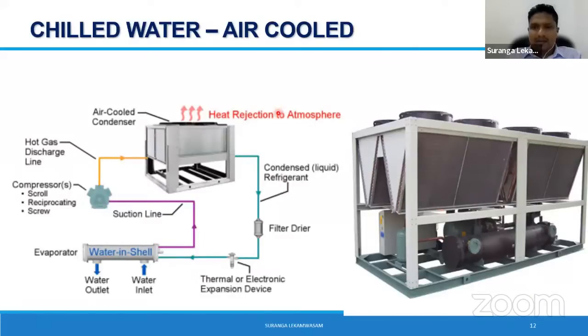They are low in efficiency, because any air-cooled machine is low in efficiency, as you are all aware. Therefore, that is not much common in Sri Lanka. But there are some applications, if you look carefully, where you cannot use water-cooled chillers. If in the area you have a water shortage, or if you have bad water quality, then this will be a choice. Again, especially in hospital applications, some of the hospital design guides recommend going for air-cooled chillers, not water-cooled chillers, because when you go for water-cooled chillers, at the cooling tower there is a risk of Legionella formation, right? That can be airborne and is not advisable in a hospital environment because people are really vulnerable.